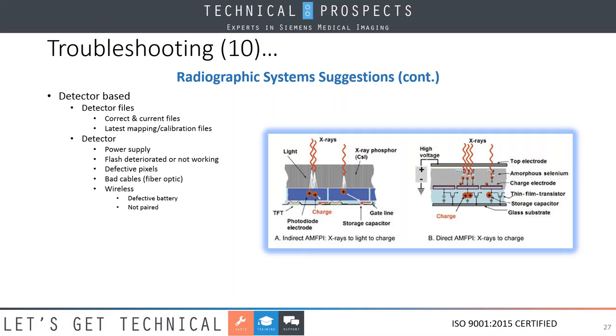Today's day and age, it's happening automatically for us, so that when you do a recalibration of a detector and things of this nature, the software is reestablishing the white and dark fields and also remapping this on a regular basis to keep it most current so that we get the best quality image. Again, you need to look at the manufacturer because some still do it manually, some still do it automatically. It's up to you to know what you have on your system.